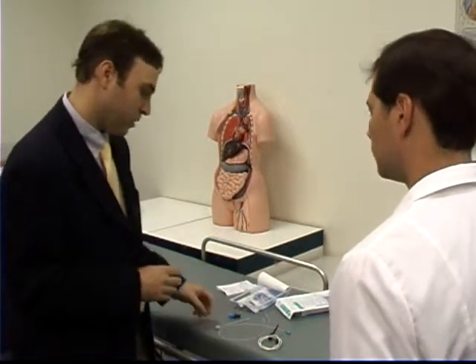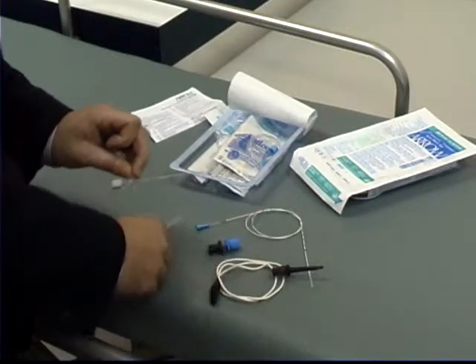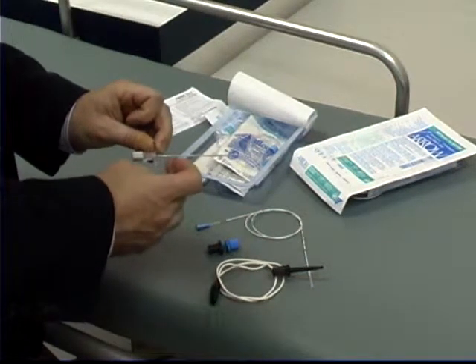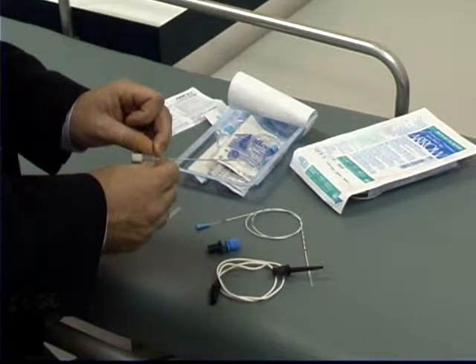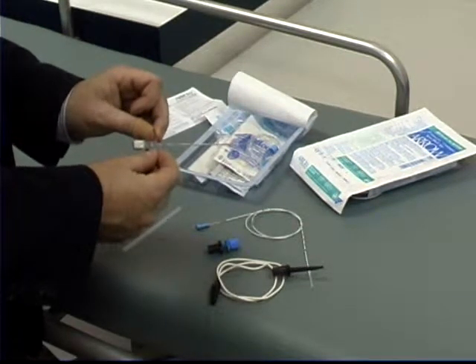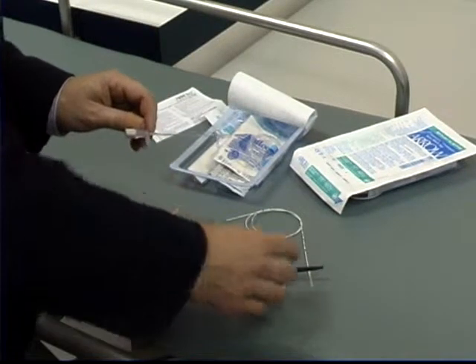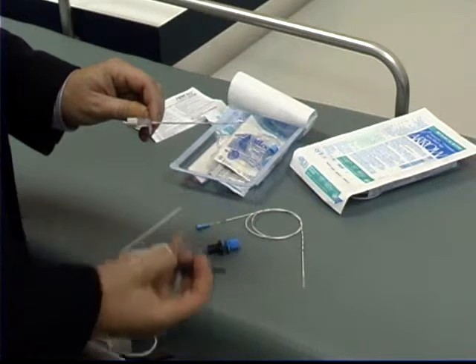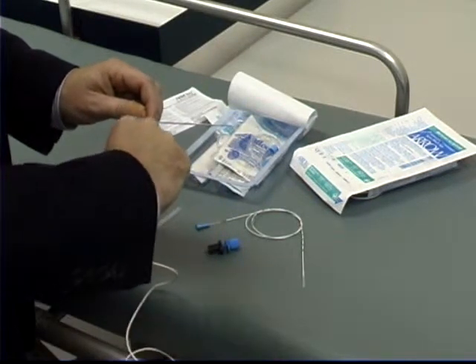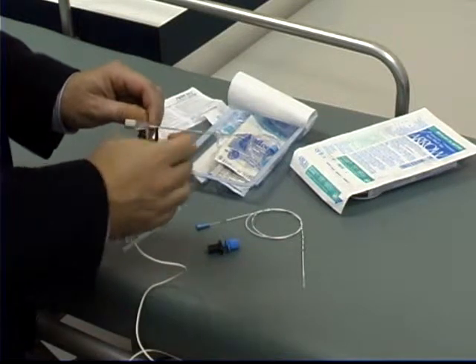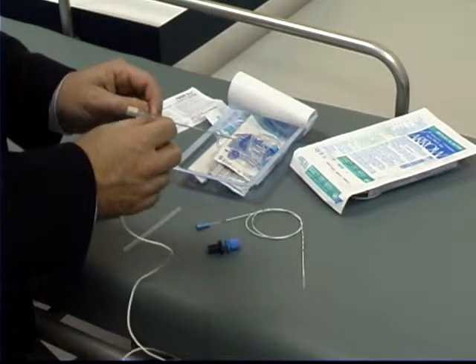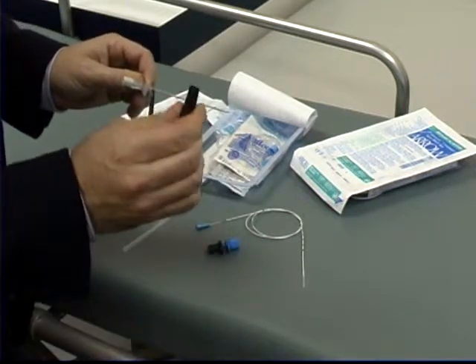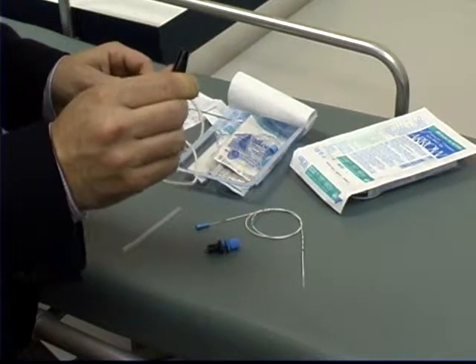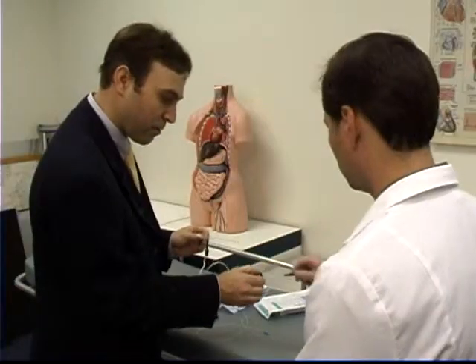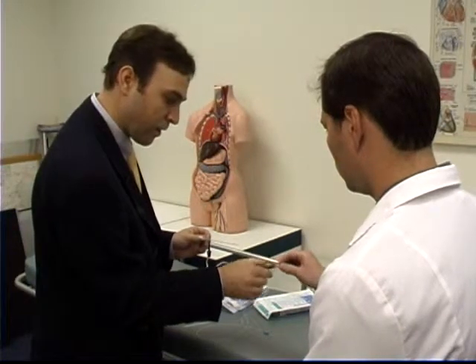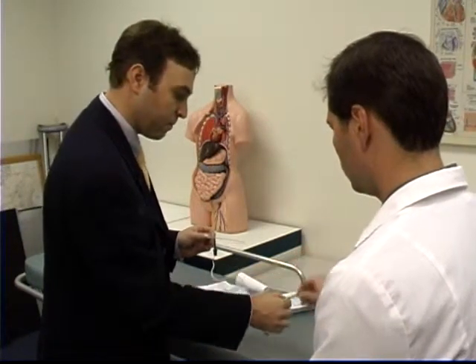I'm assuming that the components are somewhat similar. It's a 17 gauge Tuohy needle, but similar to what you described, it is insulated on the shaft. Again, I'm assuming this is similar to what you're currently using? Yes. The difference, which you described earlier, is that you have a direct wire coming off of the needle. In the case of our product, we have a snare hook that connects on the exposed portion on the most proximal end of the needle. This alligator clip will then connect onto your stimulator. Do you have a stimulator there? Yes. And so you have a male pin stimulator. That just connects right on there. And that sheath can go right over.